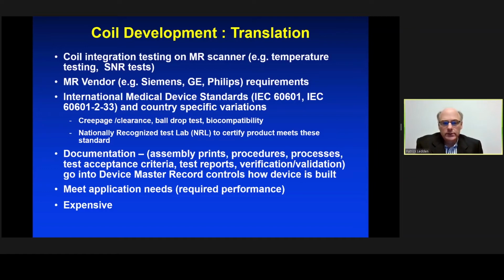Moreover, there are international medical device standards, such as IEC 60601 and IEC 60601 2-33, which is MR specific. There are a lot of country-specific variations as well. Some of these standards don't necessarily immediately apply to the MR industry, but yet the coil will still need to meet these, in particular creepage and clearance, ball drop tests, biocompatibility. These are all essential. And most of the time you end up having a nationally recognized test lab to certify the product to meet these standards.